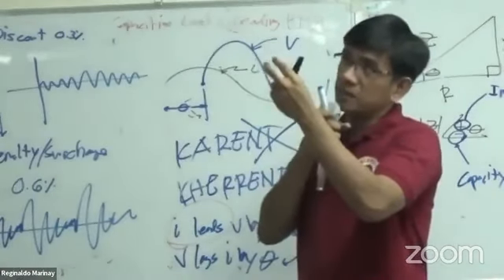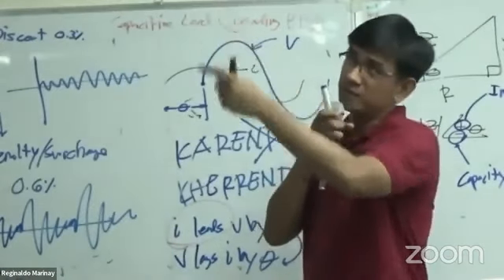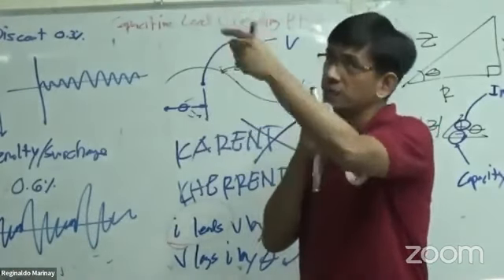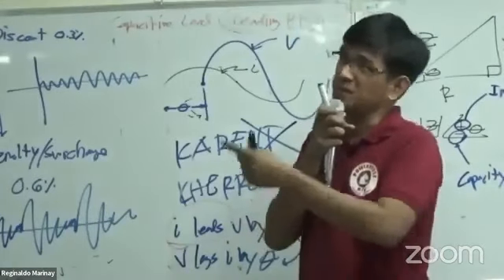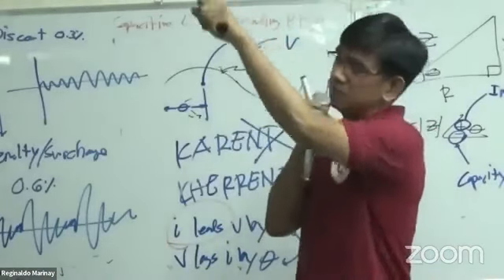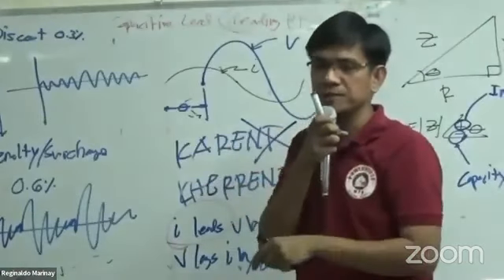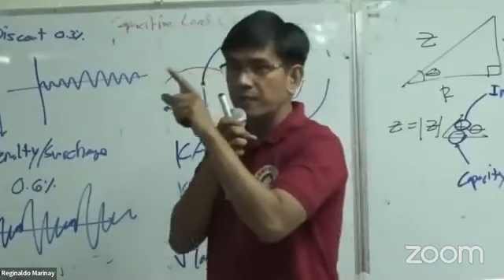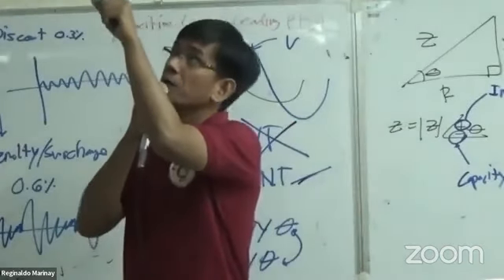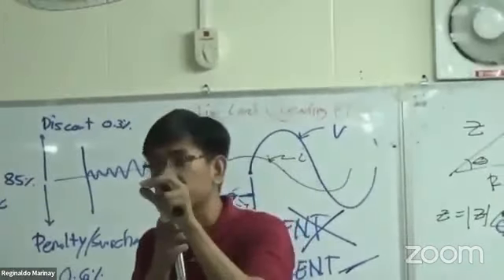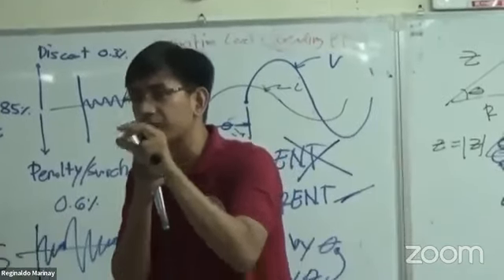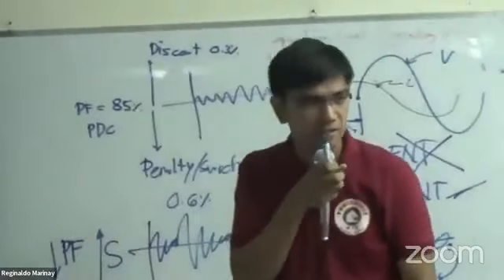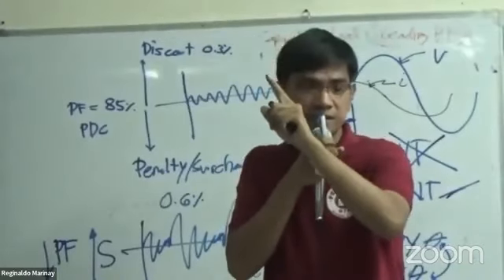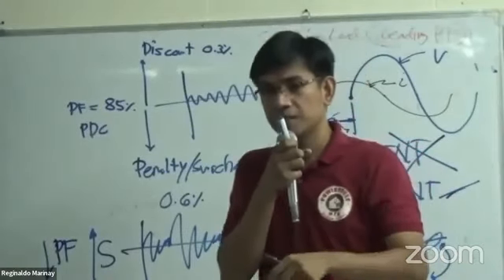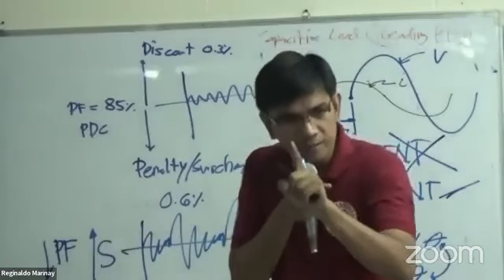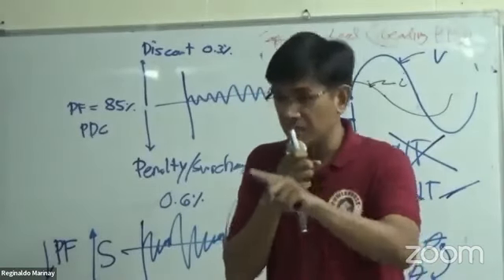Because you apply the rated voltage - if the rated voltage is 220 volts and you apply 220 volts, it will function properly. But if rated is 220 and you supply only 180, it will not work properly. What happens is if you apply a low voltage, the motor tends to draw a larger amount of current. Just like in the transformer - the lower the voltage, the higher the current.